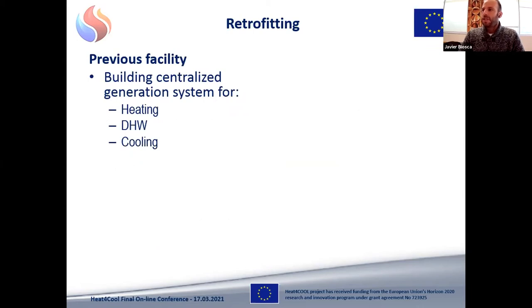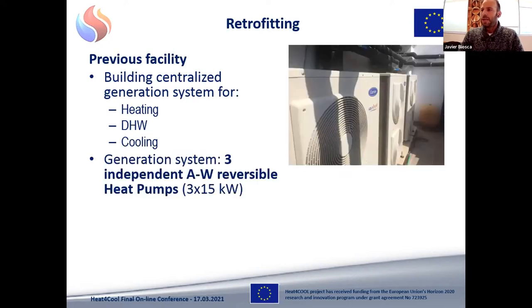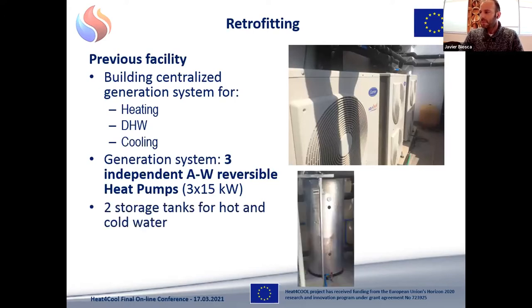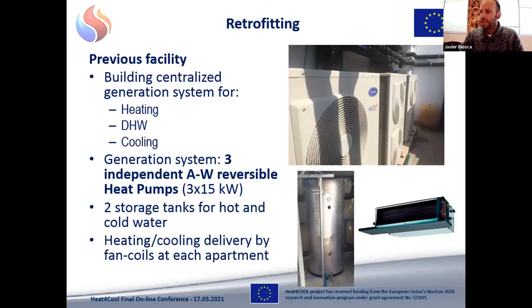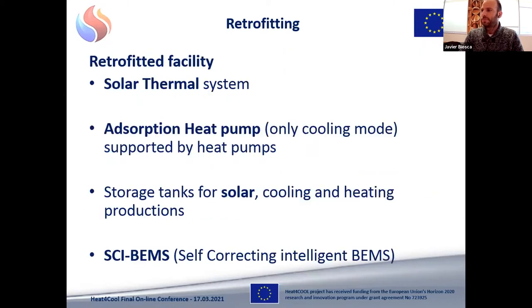The previous facility consisted in a building centralized generation system for the production of the heat transfer fluid in order to satisfy the heating and cooling demands and also the domestic hot water demand. And this generation system were 3 independent air water reversible heat pumps of 15 kilowatt each one. And there were also 2 storage tanks in order to store the hot and cold water as the heat transfer fluid for these thermal energies. And these heating and cooling thermal energies were delivered by fan coils at each apartment.